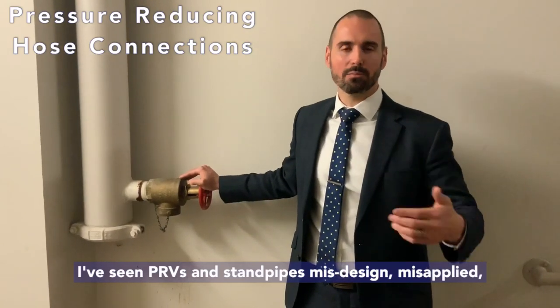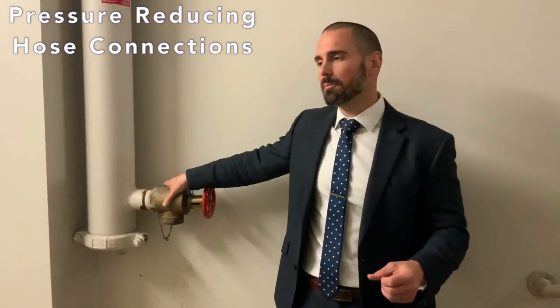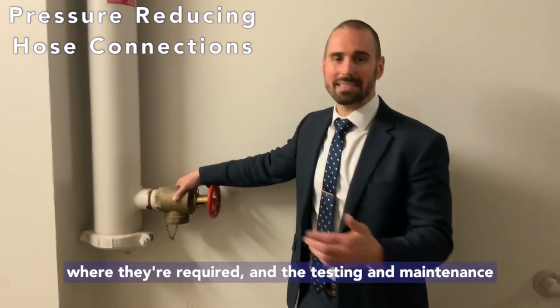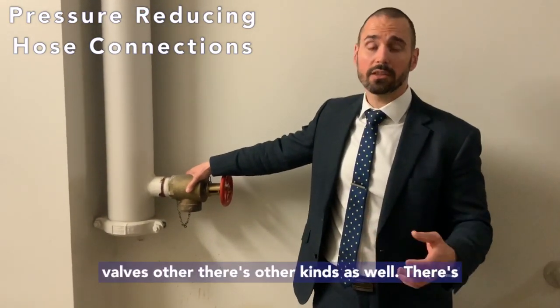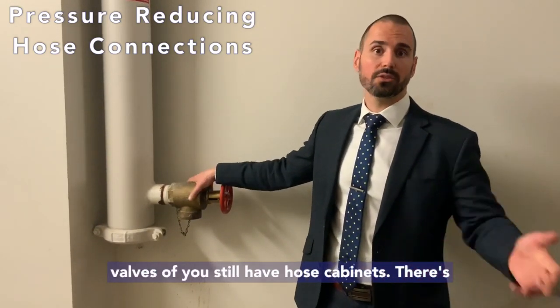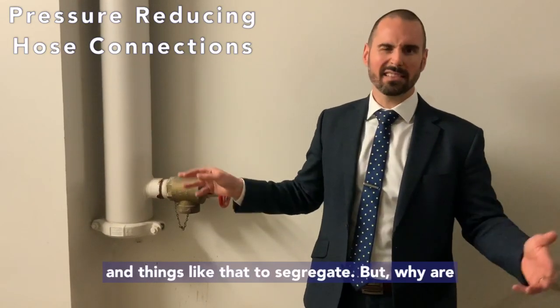This was his idea. It's one of my bigger gripes, because I've seen PRVs and standpipes misdesigned, misapplied, and mistested numerous times in numerous different hospitals. Where you're normally going to find pressure reducing valves is in high-rise applications, and we'll talk through that — when they're required, where they're required, and the testing and maintenance requirements. There's also add-on kinds, inch-and-a-half pressure reducing valves if you still have hose cabinets, and master pressure reducing valves that you can put on fire pumps or four-inch mains to segregate.